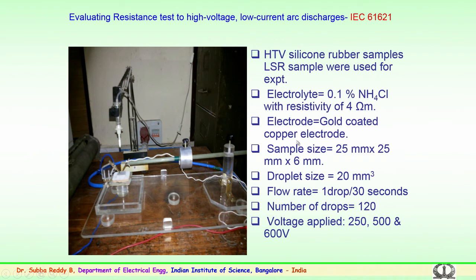Then the electrodes, as mentioned, were gold coated copper electrodes, very important. The sample size was 25 mm by 25 mm by 6 mm in thickness. The droplet size was 20 cubic millimeter, a very small droplet that falls in between the electrodes. The flow rate of the droplet is 1 drop per 30 seconds. So, you have 2 drops in a minute falling on the sample during the electrical stress. The voltage applied between the electrodes was initially 250 volts, then 500, then 600 volts. So, the voltage levels were changed, and the droplets were 120 in number. The surface changes over the 120 droplets were studied, and the evaluation of resistance was done.